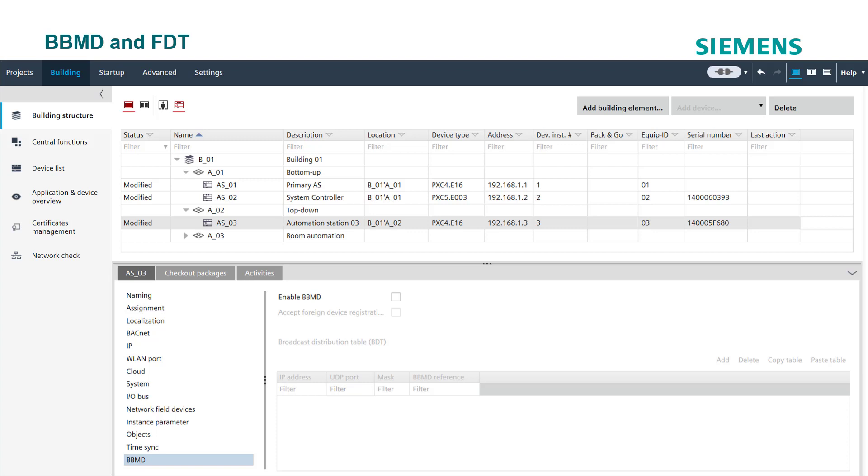The main purpose of BBMDs is to redistribute the broadcast messages that BACnet requires for discovery. To set up the BACnet IP broadcast management devices, open the device details and go to BBMD setting.